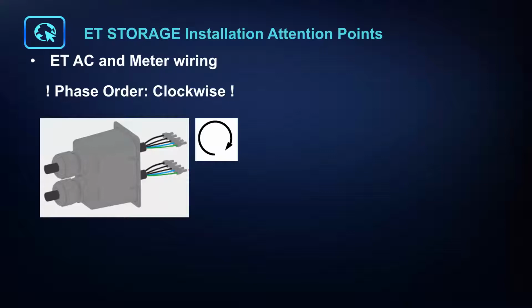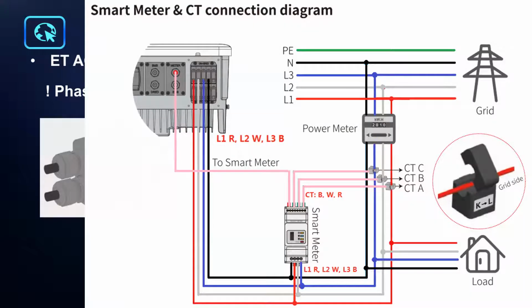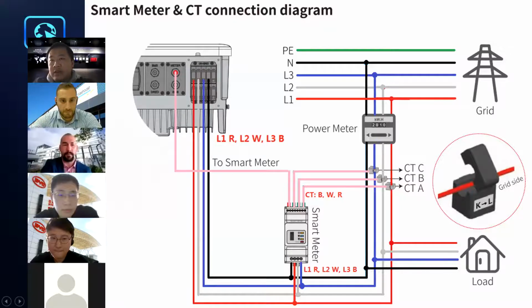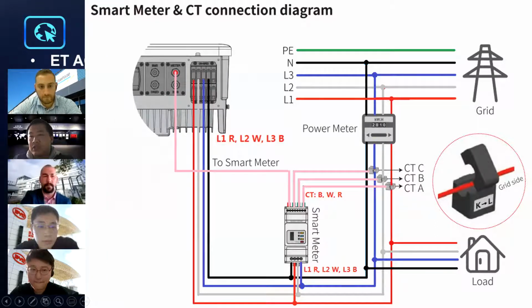Then the installer just simply swaps any two phases, either at the bottom of the inverter or in your meter box, so that the inverter can work. Another key thing for three-phase storage is that the phase order on the inverter must be 100% matched with the phase in the meter box for your smart meter. For GoodWe, we give you a CT meter in the box already. It comes with a two-wire meter together with 3 CT clamps. As the installer, you put this meter and CT into the switchboard, and its function is mainly to control battery charging and discharging. So we have to make sure the phase connected to the inverter matches the phase connected to the smart meter.